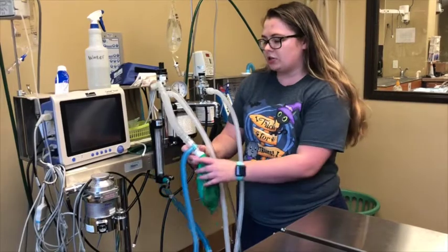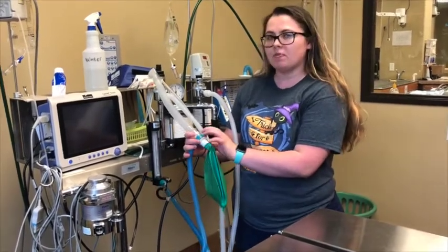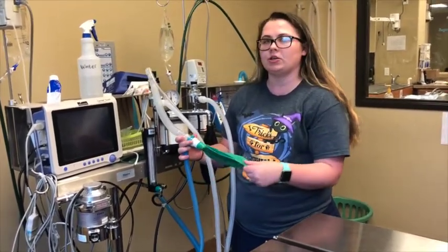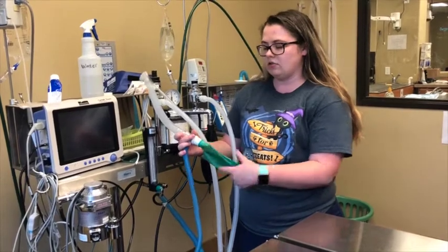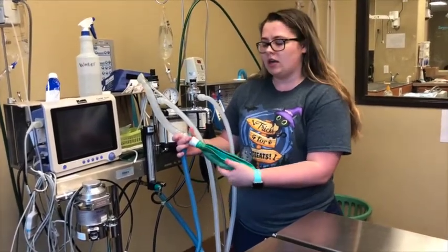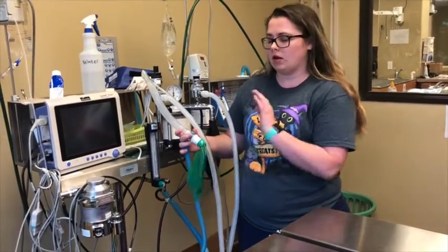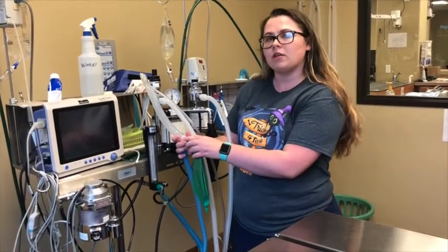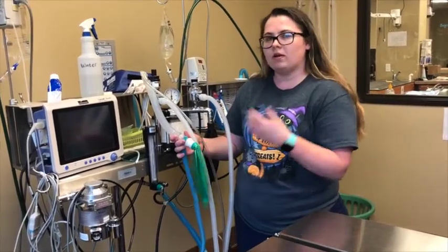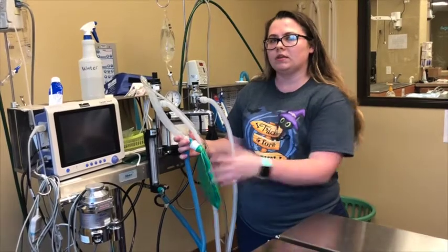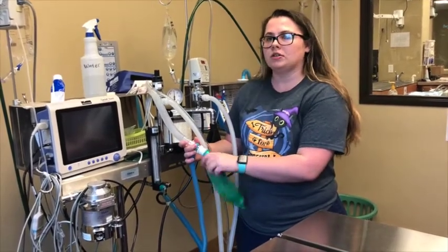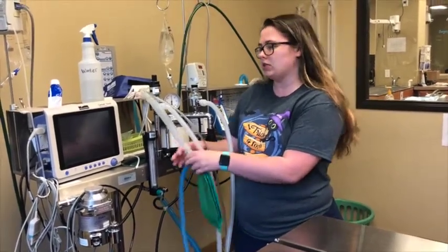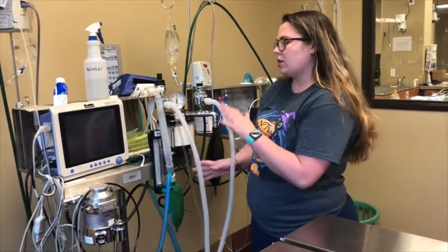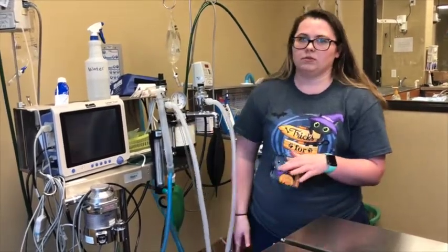You always want to make sure it has a closed and open valve. You want to make sure it's always open so the patient can breathe. If it is closed, it means you're breathing for the patient. And if you leave it closed too long when they do take breaths, they won't be able to breathe normally, and this can build up a lot of pressure in their lungs and be very deadly to our patients. So that is our rebreathing and our non-rebreathing systems.